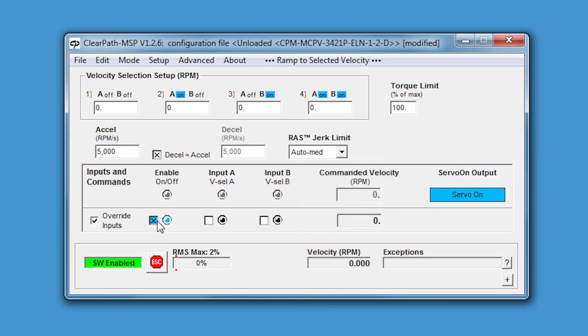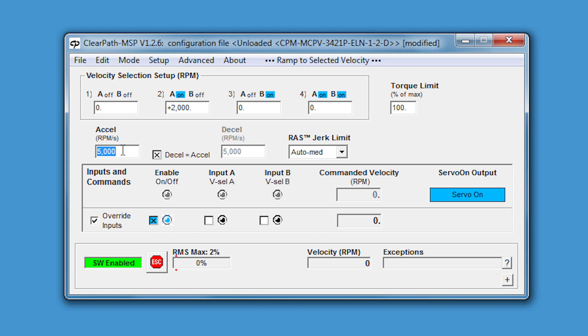I'm going to leave the number one velocity set to zero RPM, but I'll set the number two velocity to 2000 RPM. While I'm at it, I'm also going to set my acceleration and deceleration values. These determine how quickly the motor will increase and decrease from one speed to another. So, for example, if I want to accelerate from zero to 2000 RPM in half a second, I can set the acceleration to 4000 RPM per second.